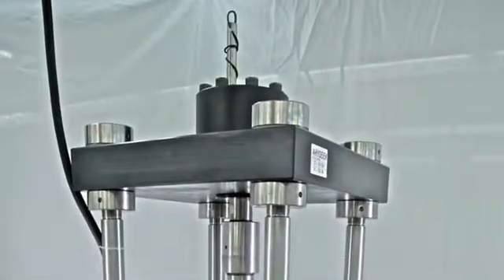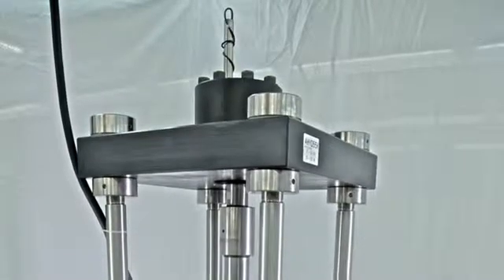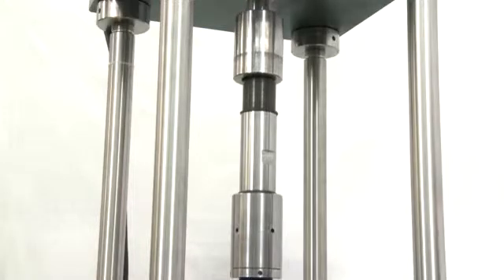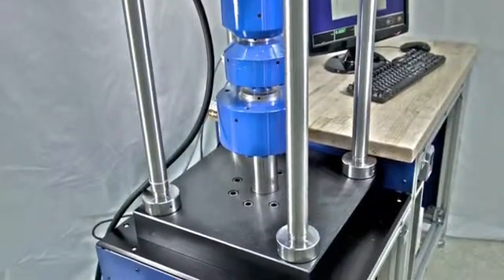At the top of the load string stack is the LVDT-based slack adapter, which assures the system always provides a true off-contact zero load condition, allowing both tension and compression calibrations with a single installation. The extremely rigid construction uses hardened stainless steel posts and steel platens.